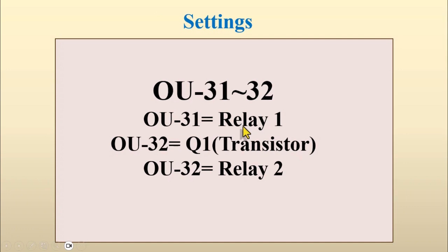If we configure the setting to the value of 12, the internal output relay of the inverter will activate as soon as the inverter begins its operation. If we have chosen to use the normally open output relay, it will close immediately, and if we have used the normally closed one, our relay will open.